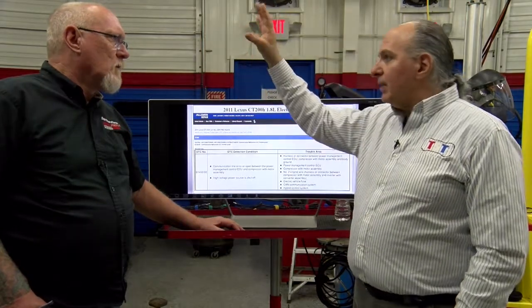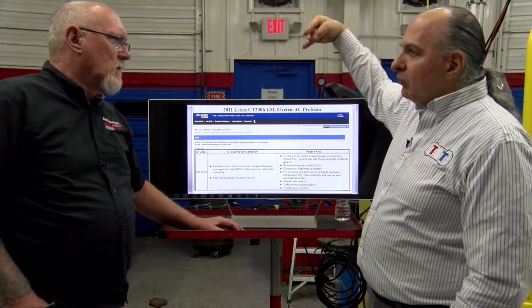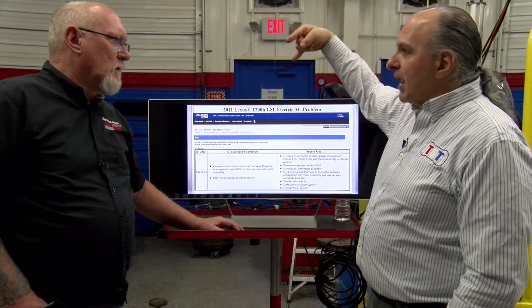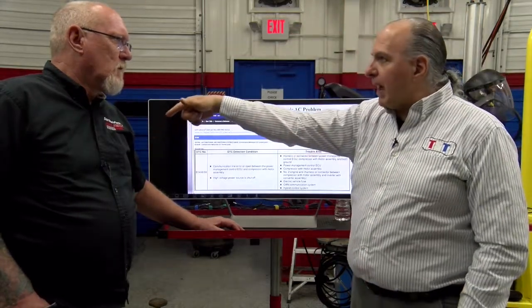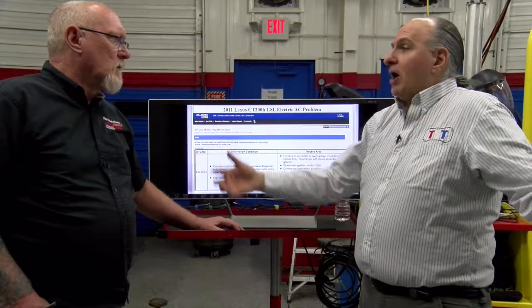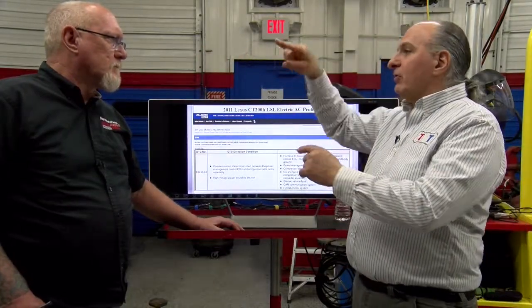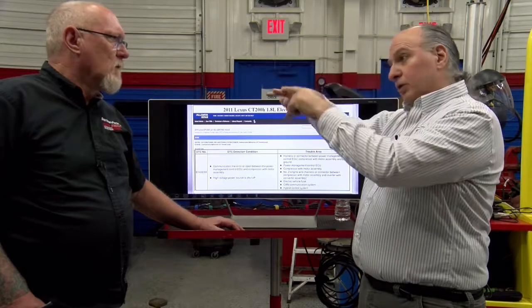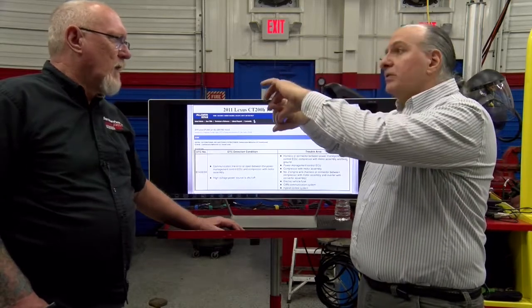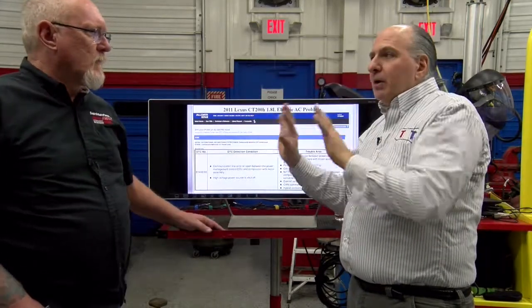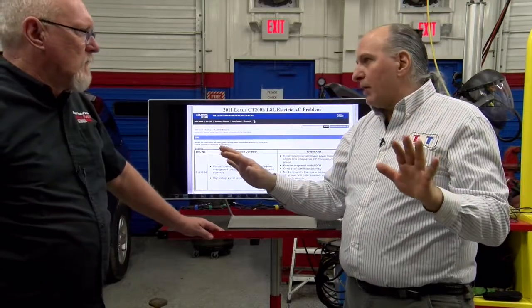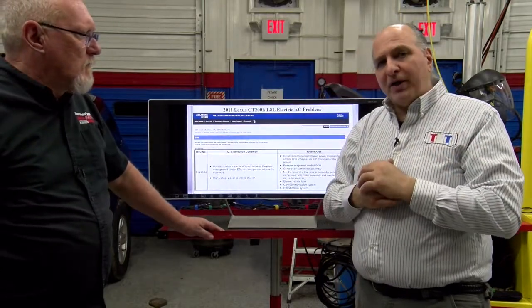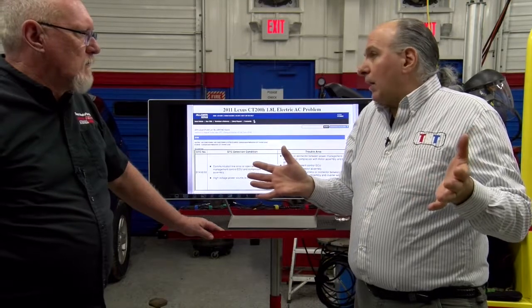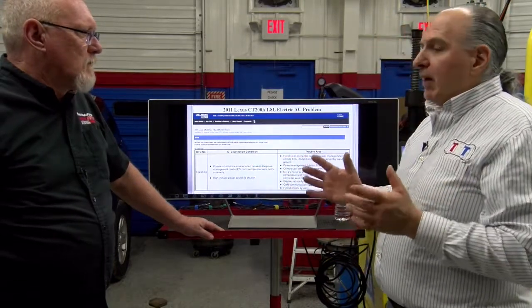I would put my other meter, my Cat 3 certified meter, another Fluke, at the other end. Take the 1587 meg ohm Fluke, put the voltage through up top. If I get voltage coming through the bottom, the wire's good. And I would check both legs. If I'm putting it through this leg, well, this one better not have it unless what? They're touching. But then I would get a short. But I still go testing it the same way. If I get voltage through both of them, it ain't the wire. I ruled the wire right out. And now I'm down to two things.